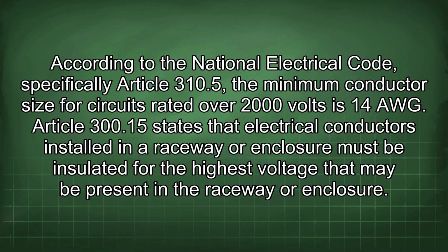According to the National Electrical Code, specifically Article 310.5, the minimum conductor size for circuits rated over 2000 volts is 14 AWG. Article 300.15 states that electrical conductors installed in a raceway or enclosure must be insulated for the highest voltage that may be present in the raceway or enclosure.